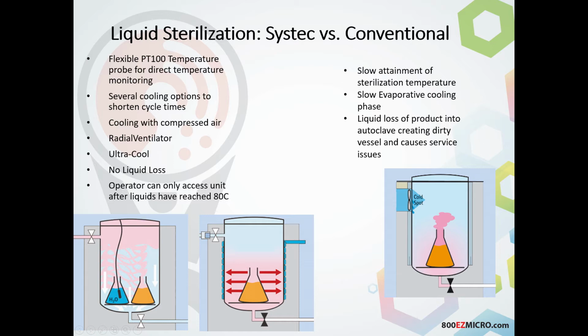One of the first ones that we offer is displayed there on the right-hand side, which is a cooling option that has cooling coils wrapped around the vessel itself. So we'll run cooling water through that. We also have the ability to fan that internal atmosphere, which allows us to use even less water to cool. Then we also have an ultra cool option as well. Again, no liquid loss at this point. We also maintained our temperature at 121 with a flexible PT100 temperature probe. Then we cooled it down to 80 degrees prior to allowing the end user to have any access. This allows us to make sure that we have a very safe process.